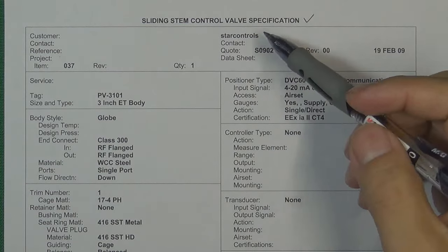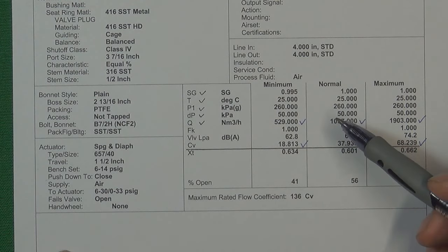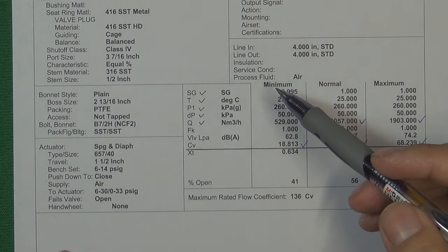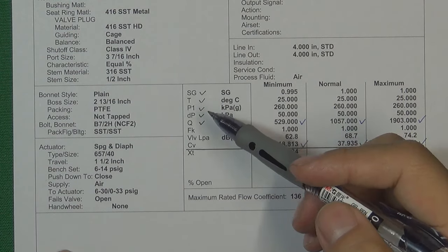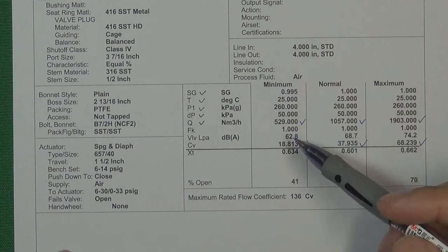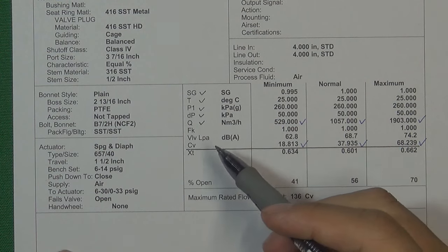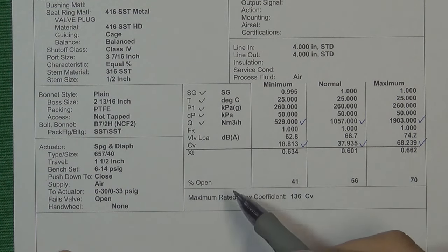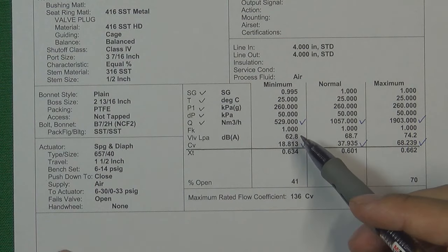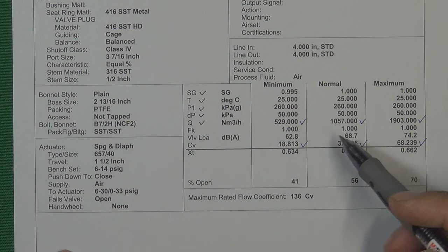Here is a real control valve specification to understand how to choose a correct control valve according to the flow medium CV. It includes a lot of information about this control valve. When customers choose a control valve, they tell the valve manufacturer the minimum, normal, and maximum flow capacity. The valve manufacturers use those five design factors to calculate the minimum CV, the normal CV, and the maximum CV, then choose a correct control valve to match the flow medium CV. This valve, when it opens to 41%, gets the minimum CV; when it opens to 70%, it gets the maximum CV.